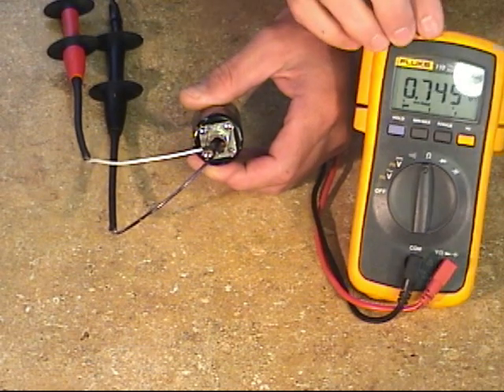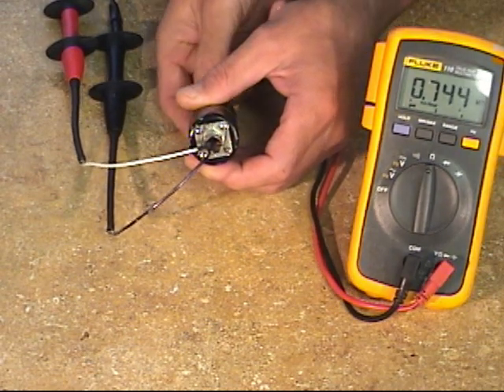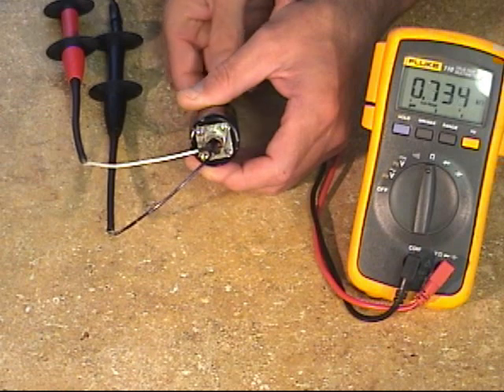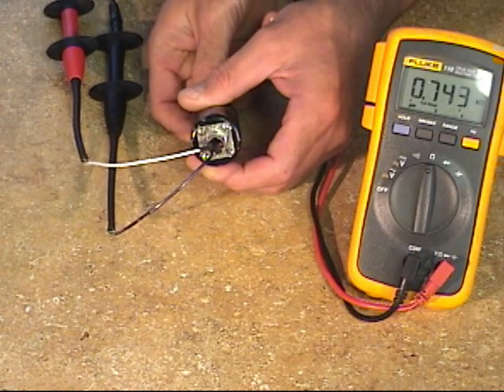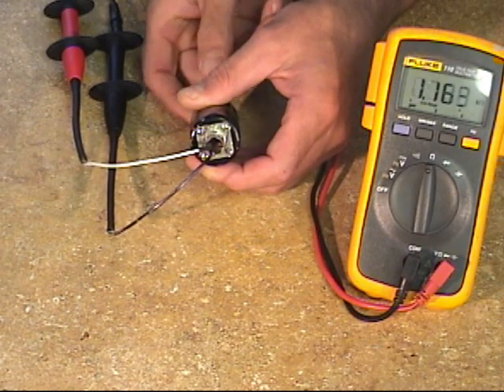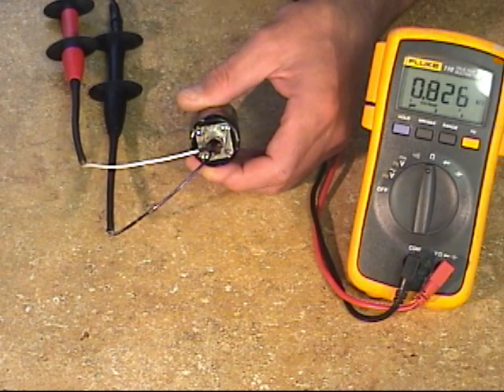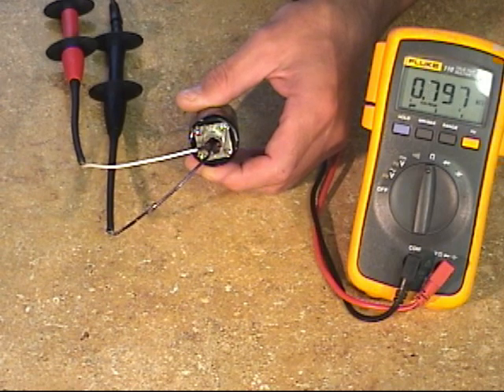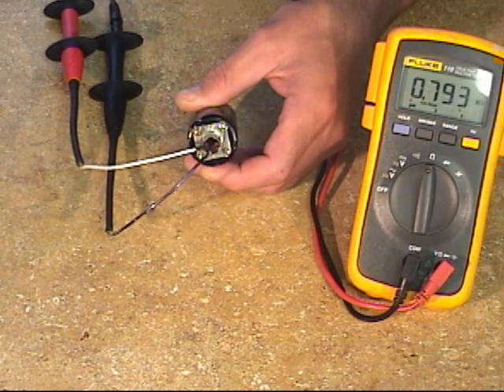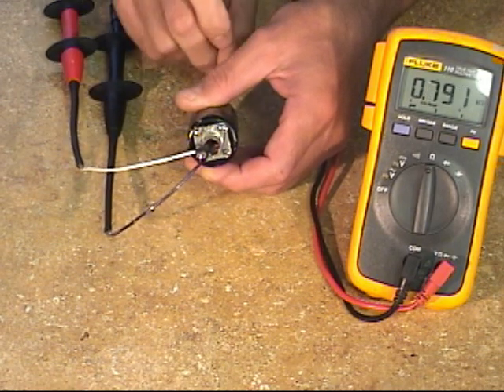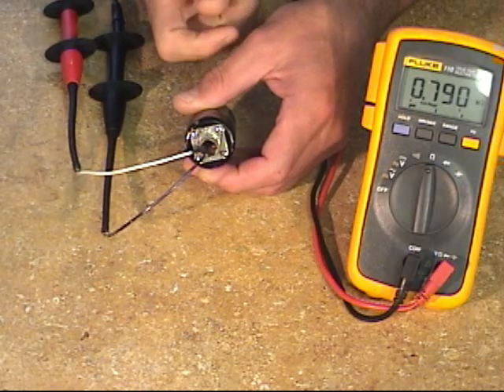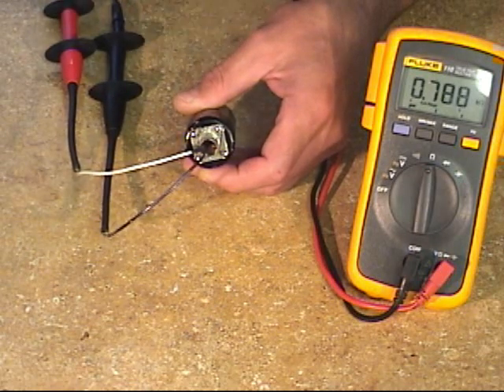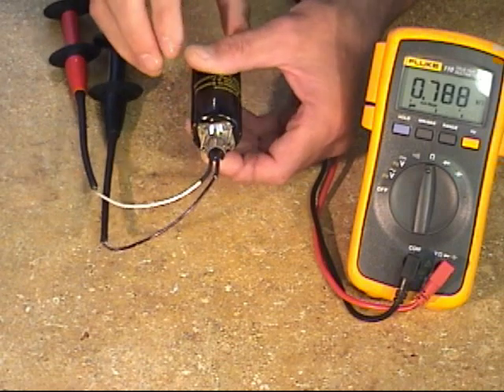So there we see a 745, that's upper limit. 744. Now what I'm doing is turning it. There's an 830, so that's out of there. This transducer's generator is a little bit high resistance. Notice I'm moving the transducer a small tenth of a turn or less, then letting go of it, then observing the resistance.